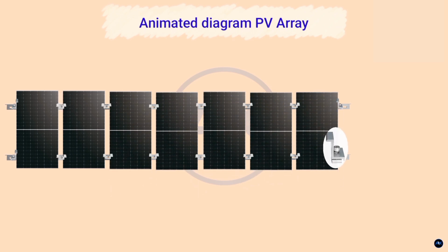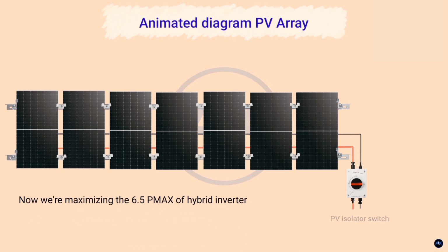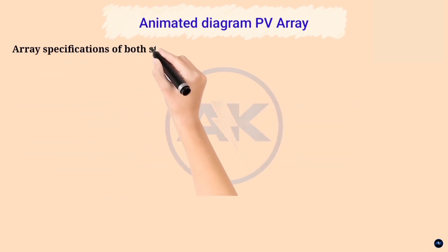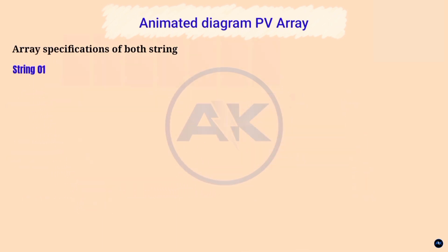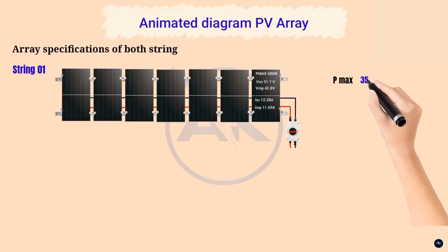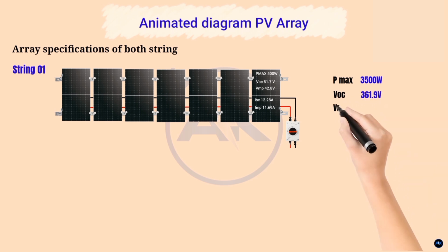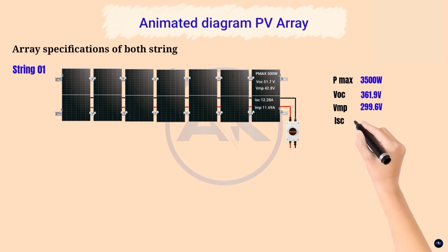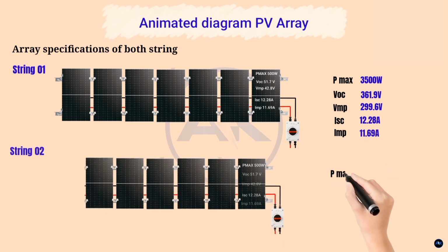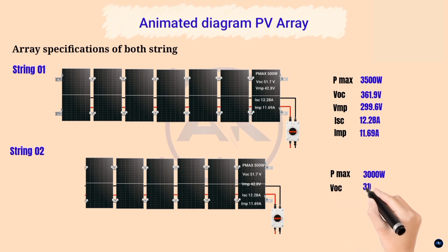So we're going to connect the positive line and then the main negative line, and this is going to our PV isolator switch. Now we are maximizing the 6.5 kW Pmax of the hybrid inverter. And here are the array specifications of both strings. String 1 array specification: we have a Pmax of 3500 watts or 3.5 kilowatts, VOC 361.9 volts, VMP of 299.6 volts, ISC of 12.28 and IMP of 11.69. String 2 array specification: we have a Pmax of 3000 watts or 3 kilowatts, VOC 310.2 volts, VMP of 256.8 volts, ISC of 12.28 and IMP of 11.69.